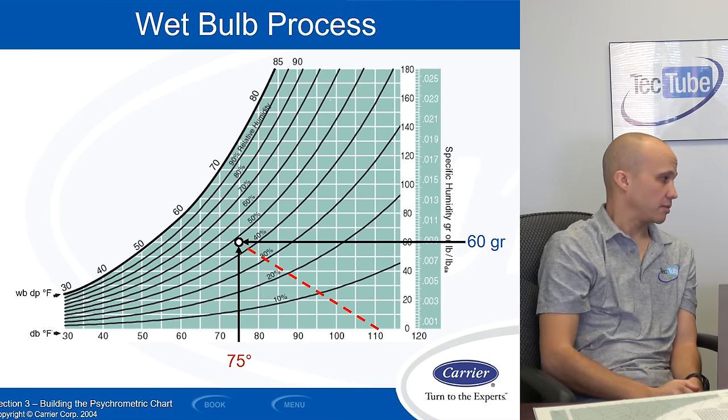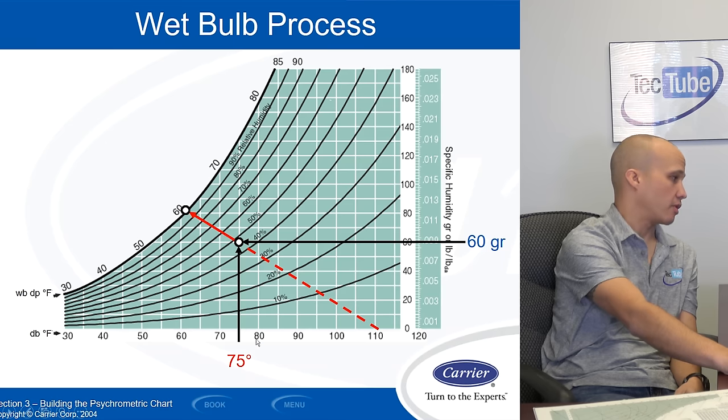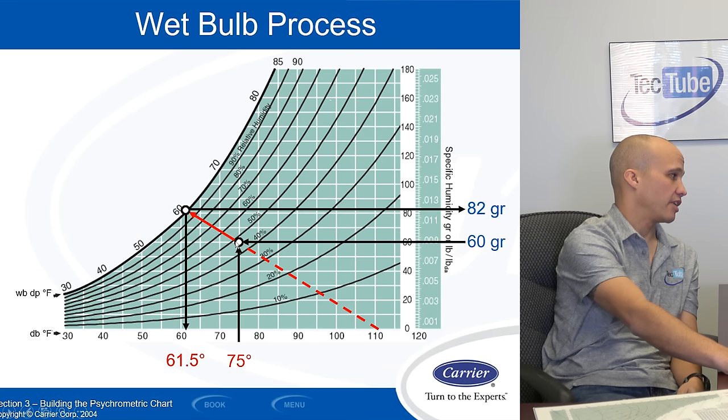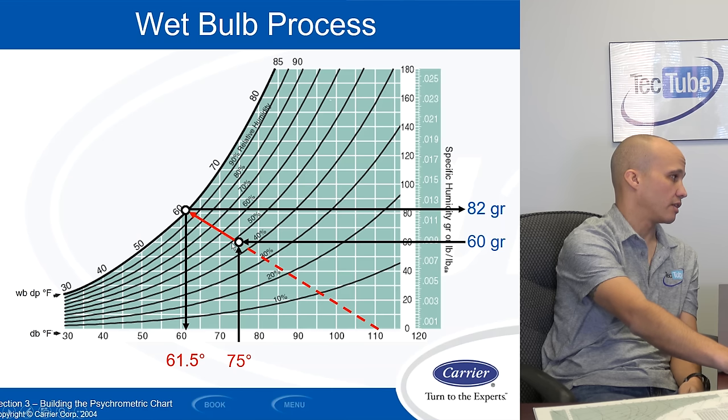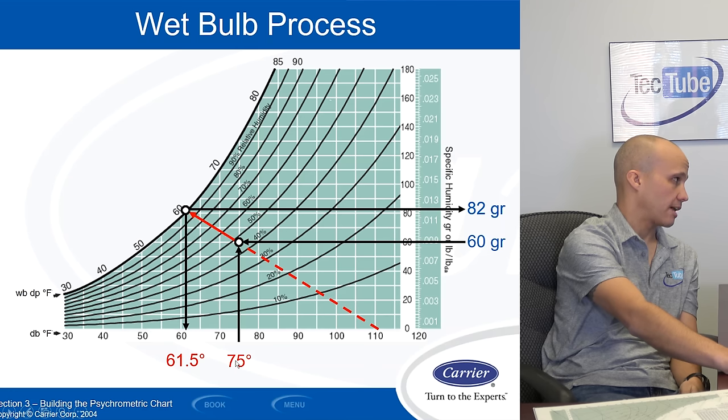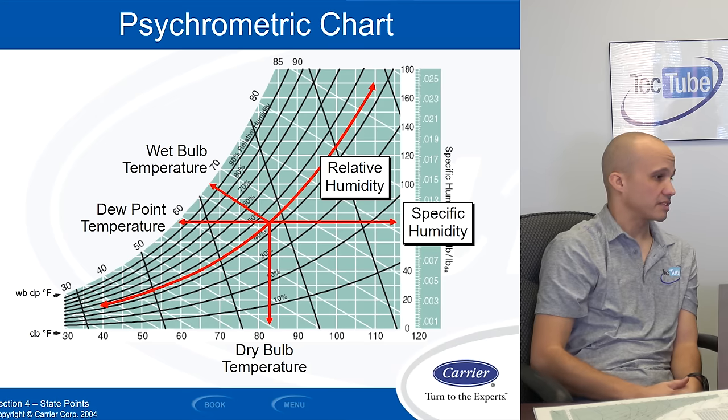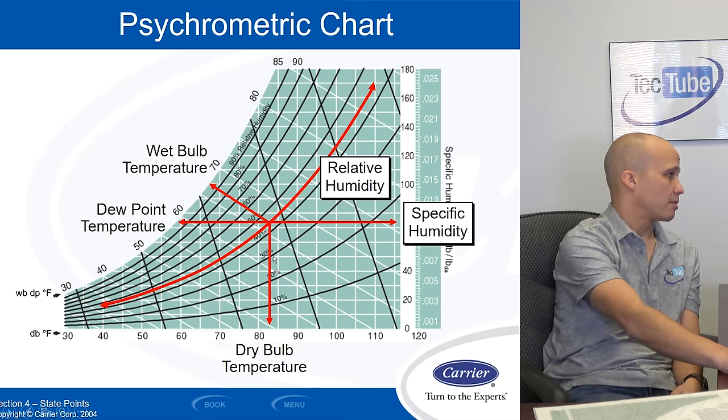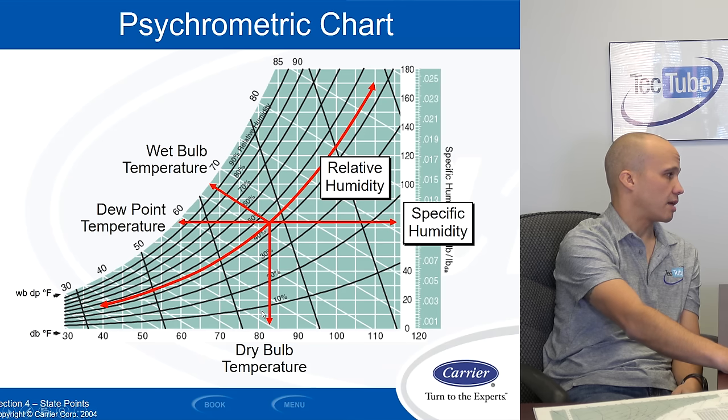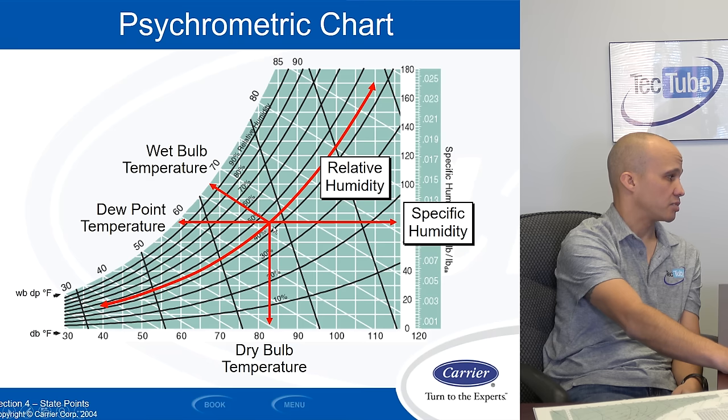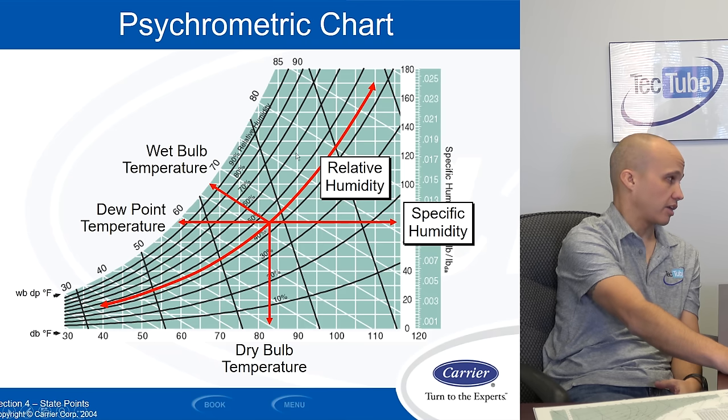The wet bulb is right on the chart in a little bit of a different way. So that same point we talked about before, 75 degrees with 60 grains of moisture. If I read across this way, I get the dew point of 53. But if I read up this 45 degree angle line, I get to a wet bulb of 61. So wet bulb is read on the diagonal line. Dew point is read straight across. Temperature is read straight down. So if you look at all of them at the same time, wet bulb is measured on the diagonal. Dew point straight to the left. Dry bulb straight down. Relative humidity is the curved line. Specific humidity, actual humidity, is horizontally across to the right.